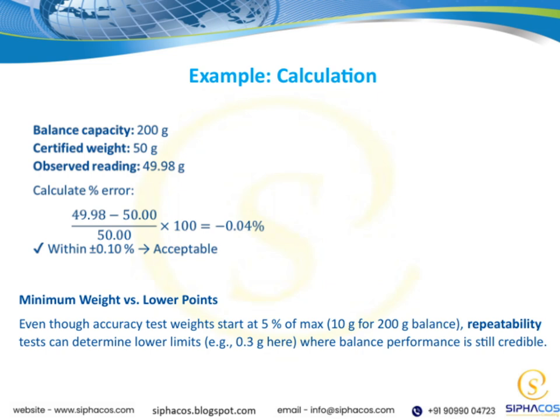For example, in this calculation, we see how we determine whether weights below that 5% threshold can still be used confidently. The key idea is that while the initial weight setting is a good starting point, we don't have to stick strictly to it. Instead, we evaluate the balance's repeatability at lower weights to ensure accuracy and reliability, especially when working with very small samples or measurements.